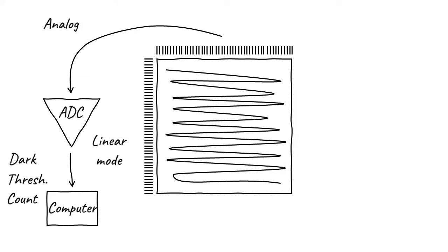But we want counting mode, because it delivers significantly better data quality. So the computer subtracts the background, performs thresholding to separate the noise from the signal, finds the bright spots in each frame, and centroids each bright spot to produce a counted frame. By summing many of these counted frames, the computer can save dose-fractionated counting movies suitable for cryo-EM and other methods.